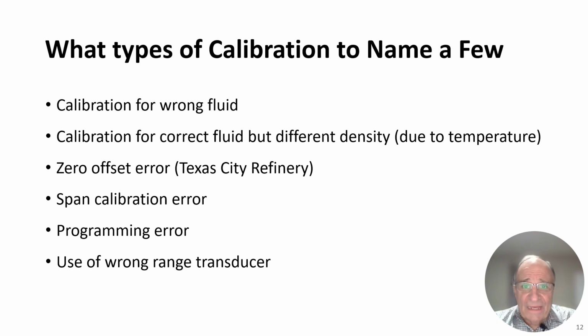There are many, many types of calibration errors that you need to be concerned about. One of them is shown here, calibration for the wrong fluid. So I set up my equipment perfectly to measure the fluid level, and I'm setting it up for water when what I'm really measuring is water glycol. So there's an error right there. And if you don't catch that error, it can carry on for years as the same maintenance person comes and calibrates the same piece of equipment for the wrong fluid. Calibration for the correct fluid, but different density. Let's say it's calibrated for a fluid that's at ambient temperature when the fluid is actually at 200 degrees Fahrenheit. That would be a density difference due to temperature.